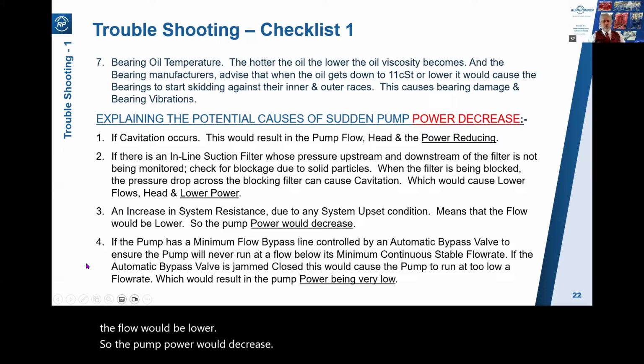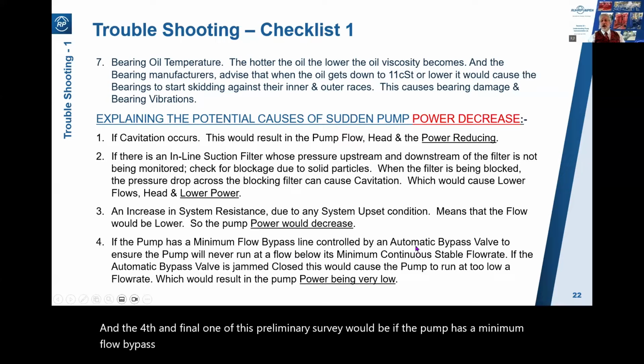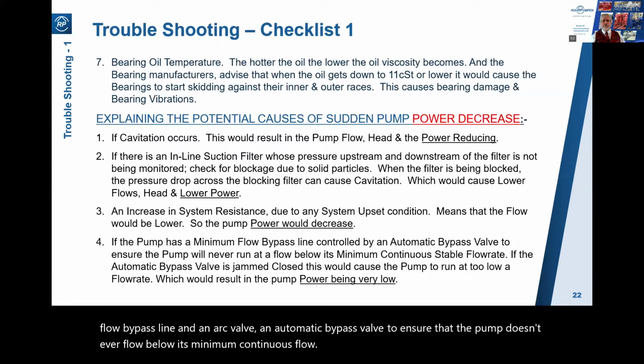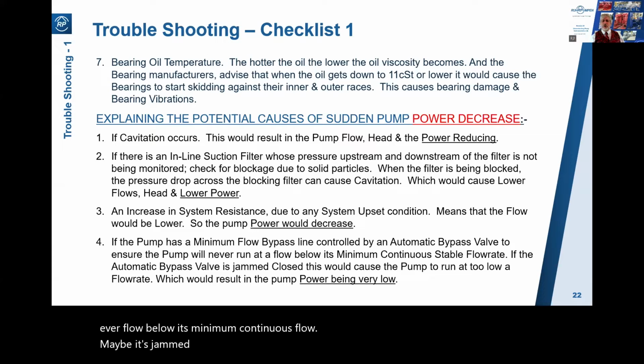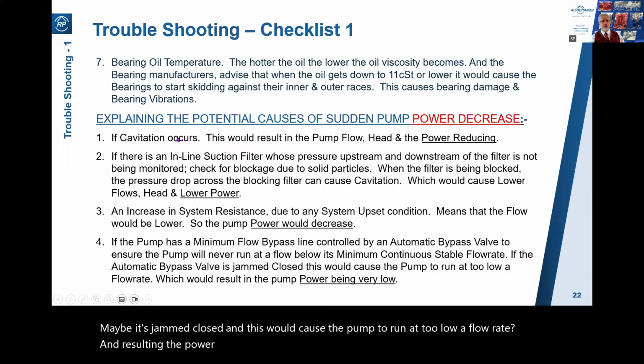And the fourth and final one of this preliminary survey would be if the pump has a minimum flow bypass line and an ARC valve, an automatic bypass valve, to ensure that the pump doesn't ever flow below its minimum continuous flow. Maybe it's jammed closed. And this would cause the pump to run at too low a flow rate and result in the power being very low. So there's 4 initial possibilities to look at.